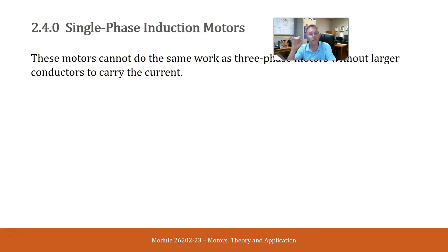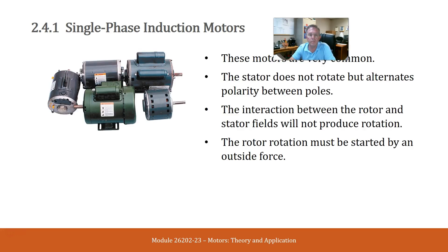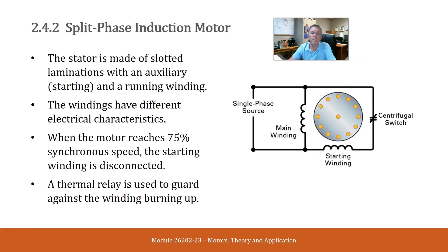Single phase induction motors. These motors cannot do the same work as three-phase motors without larger conductors to carry the current. These motors are very common. The stator does not rotate but alternates polarity between poles. The interaction between the rotor and stator fields will not produce rotation, so the rotor rotation must be started by an outside force. The stator is made of slotted laminations with an auxiliary starting and running winding. The windings have different electrical characteristics and the motor reaches 75% of synchronous speed, at which point the starting winding is disconnected. A thermal relay is used to guard against the windings burning up.